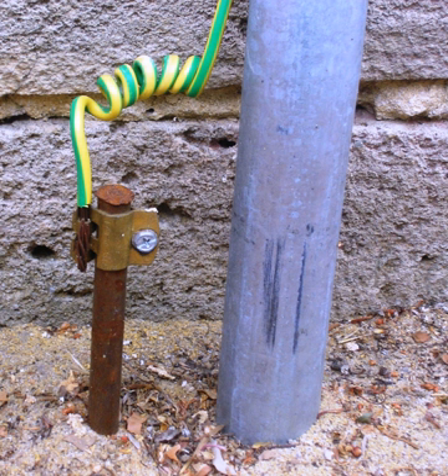The gradient of the voltage, changing voltage within a distance, may be so high that two points on the ground may be at significantly different potentials, creating a hazard to anyone standing on the ground in the area. Pipes, rails, or communication wires entering a substation may see different ground potentials inside and outside the substation, creating a dangerous touch voltage.